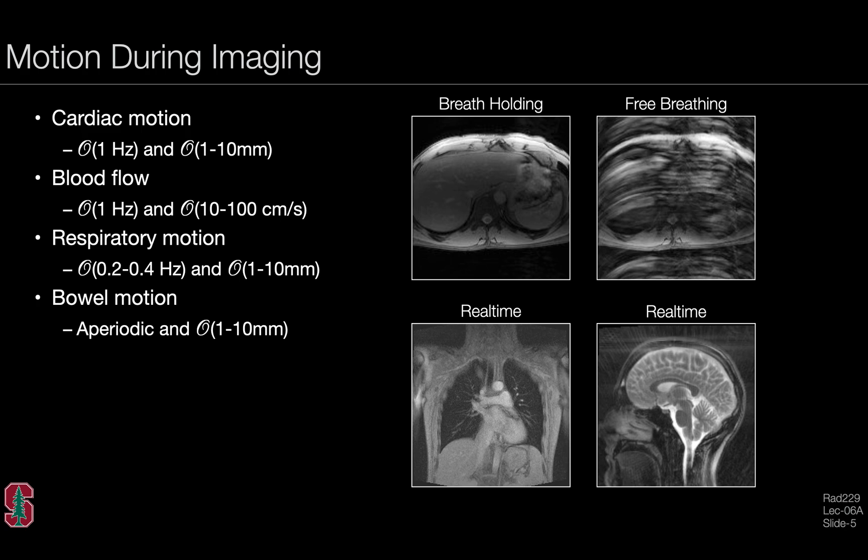In imaging, we encounter cardiac motion, that's on the order of about a hertz and spans something like one to 10 millimeters of motion displacement. We also have blood flow, on the order of about a hertz, spanning about 10 to 100 centimeters per second. There's many different kinds of underlying motion, including respiratory motion, bowel motion, patient motion, and swallowing. When imaging a particular target territory, it's very likely that there will be moving tissues or motion in the field of view. If not appropriately accounted for, this can lead to imaging artifacts.